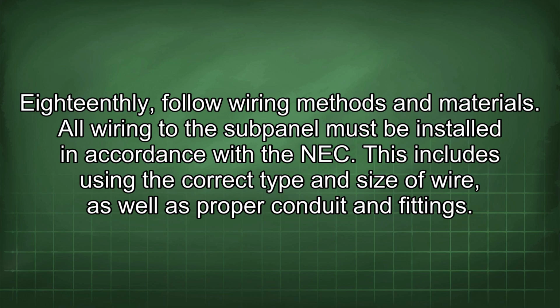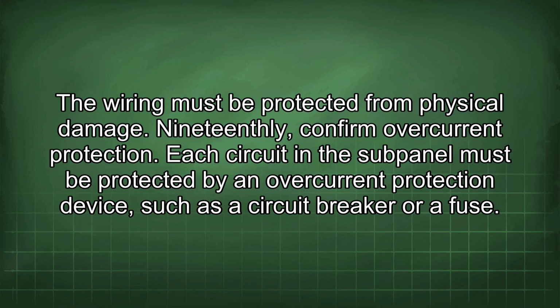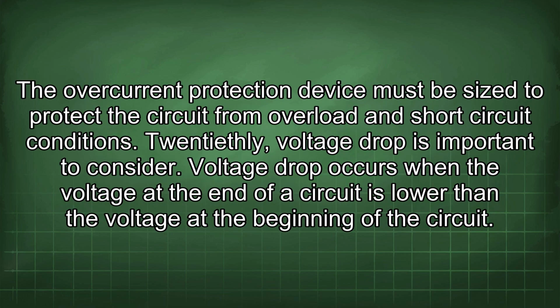All wiring to the subpanel must be installed in accordance with the NEC. This includes using the correct type and size of wire, as well as proper conduit and fittings. The wiring must be protected from physical damage. 19thly, confirm overcurrent protection. Each circuit in the subpanel must be protected by an overcurrent protection device, such as a circuit breaker or a fuse. The overcurrent protection device must be sized to protect the circuit from overload and short circuit conditions.